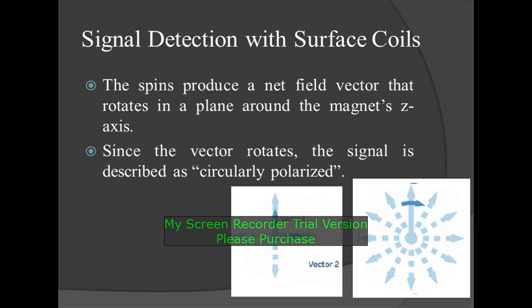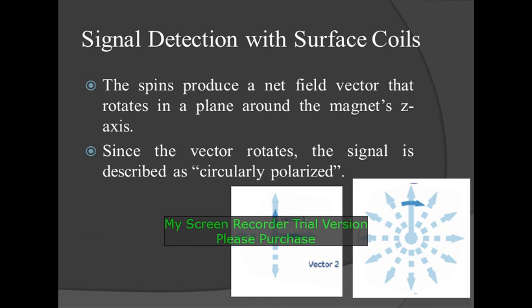Signal detection with surface coils: the spins produce a net field vector that rotates in a plane around the magnet's Z axis. Since the vector rotates, the signal is described as circularly polarized. The net field vector can be resolved into two orthogonal oscillating vectors and can be oriented in any direction in a plane orthogonal to the magnet's Z axis, as long as the two vectors remain orthogonal. When one vector is at maximum, the other is at minimum.